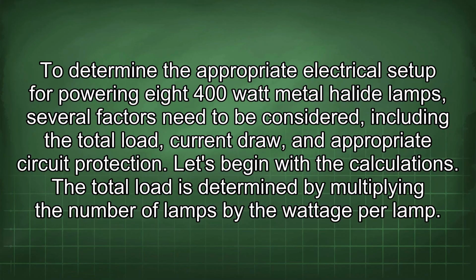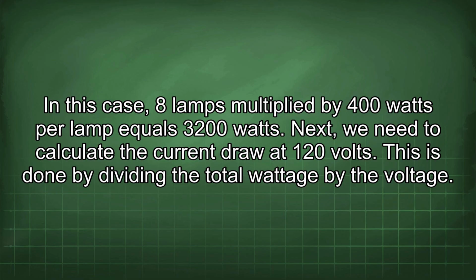To determine the appropriate electrical setup for powering 8 400-watt metal halide lamps, several factors need to be considered, including the total load, current draw, and appropriate circuit protection. Let's begin with the calculations. The total load is determined by multiplying the number of lamps by the wattage per lamp. In this case, 8 lamps multiplied by 400 watts per lamp equals 3,200 watts.